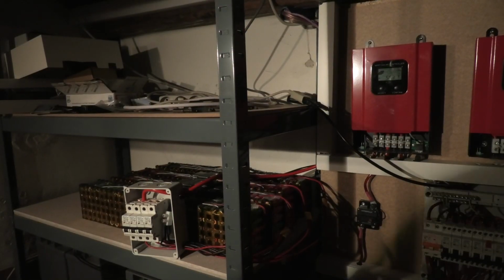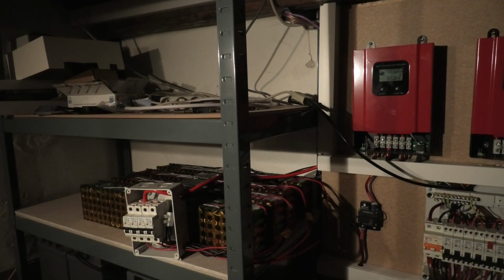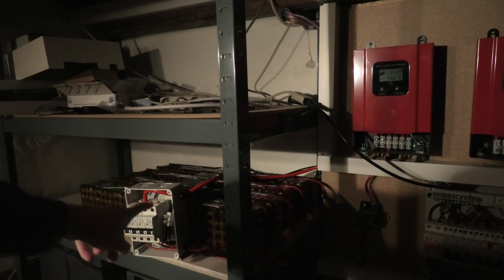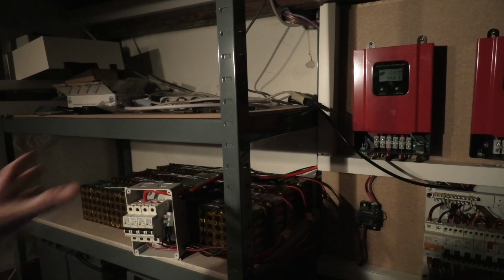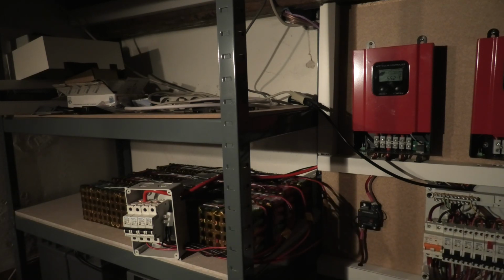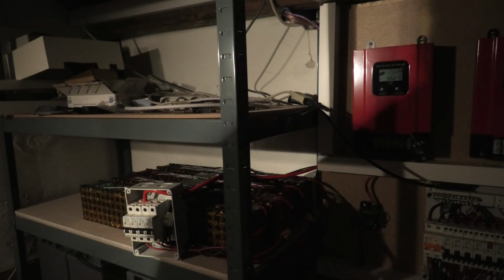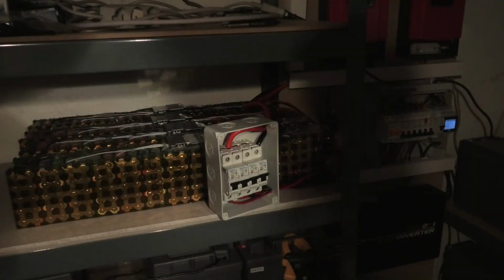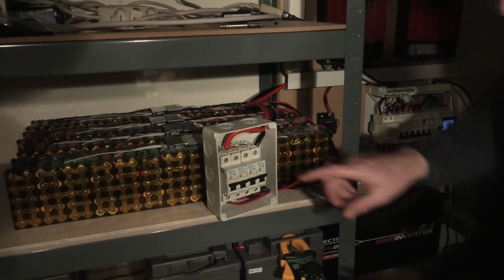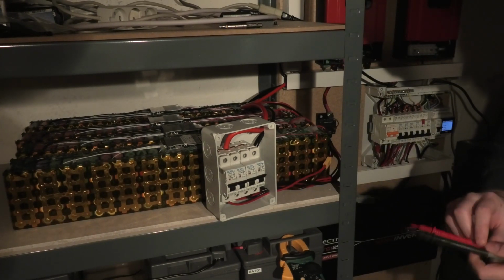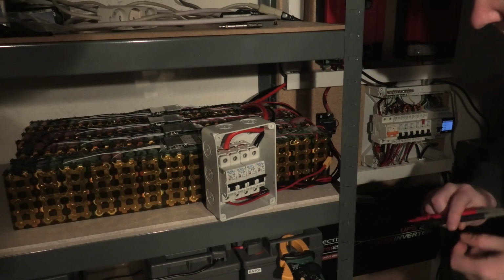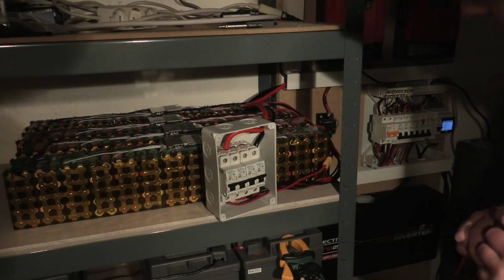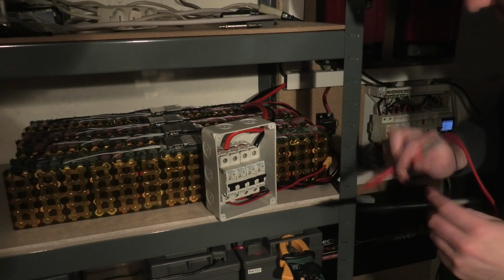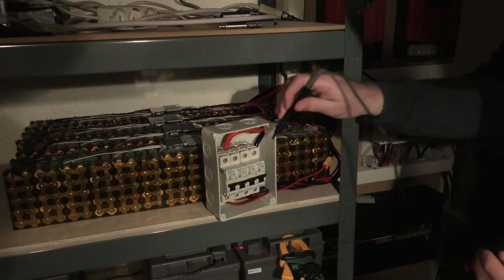So in here in the battery room, I have these 4 banks up and running. I have been negotiating with myself if I could fit another bank in here and put it on the shelf. Negotiations are still going on, but I want to check if there's any of the banks that are not good. So what I'm gonna do is turn them off, measure the voltage of the whole bank, and then disconnect the one with the lowest voltage and check it out, making sure that it's not too bad.